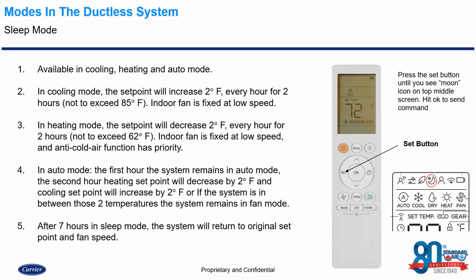Now, what the sleep is, it is available in cooling, heating, or in the auto modes. Now, in the cooling mode, the set point will increase 2 degrees every hour for 2 hours, not to exceed 85 degrees. Now, if that indoor temperature goes over 85 degrees, it will then kick on cooling to bring it back down to 85 and then resume holding 85 or below. The indoor fan is fixed at a low speed during the sleep mode and the cooling mode.